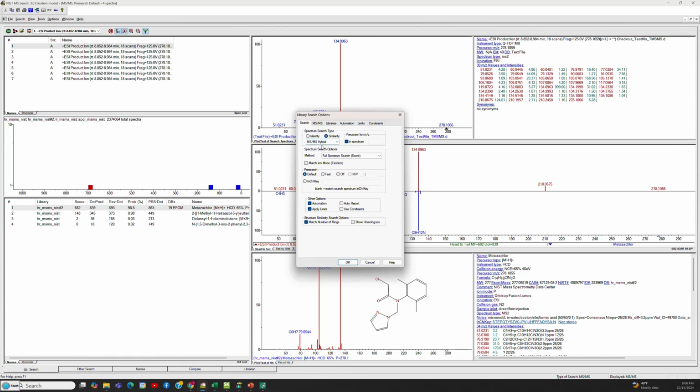if the spectrum wasn't in the library, then it would find things that are similar. Maybe if it had an additional chlorine on it, you would find it and you would see the difference in mass between your unknown and your known was 34, a chlorine minus a hydrogen. And it gives you ideas about things that are not in your database. So it greatly extends the ability of your databases to find things that might not actually be present with the exact structure.